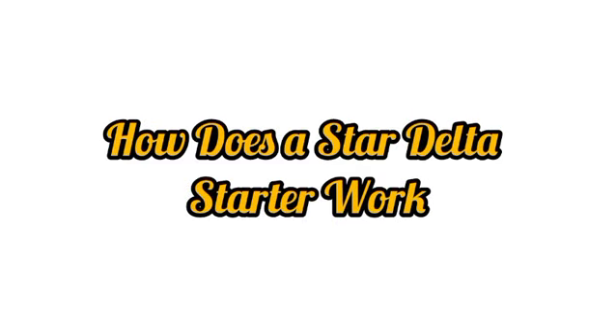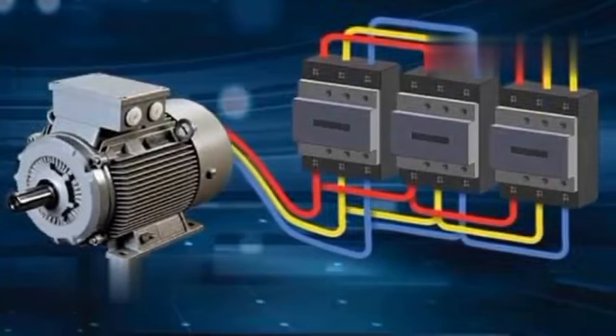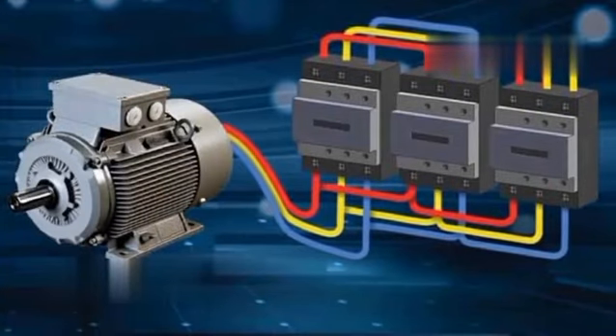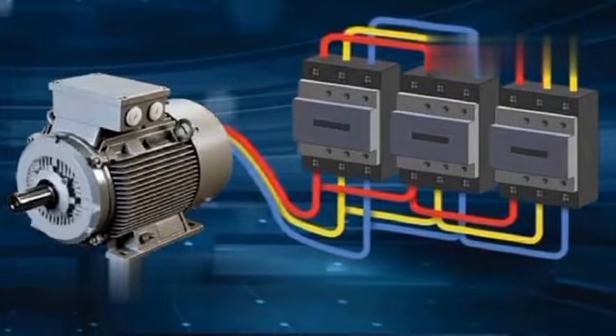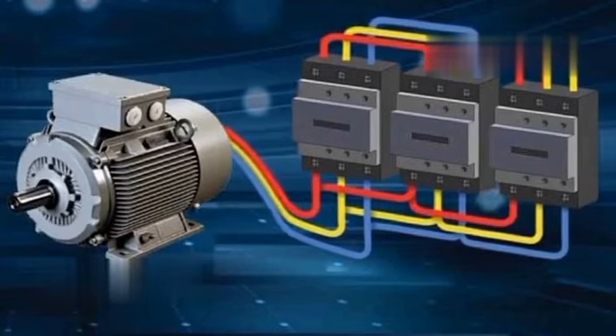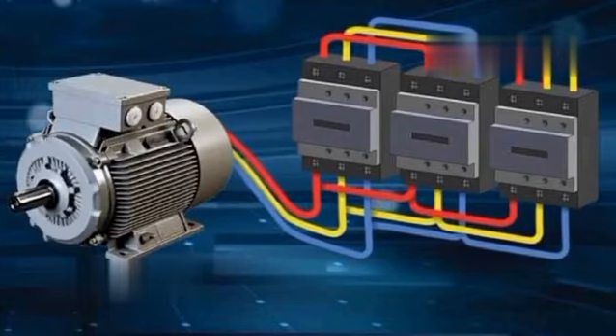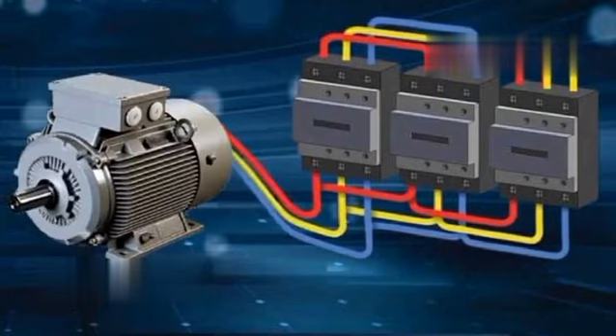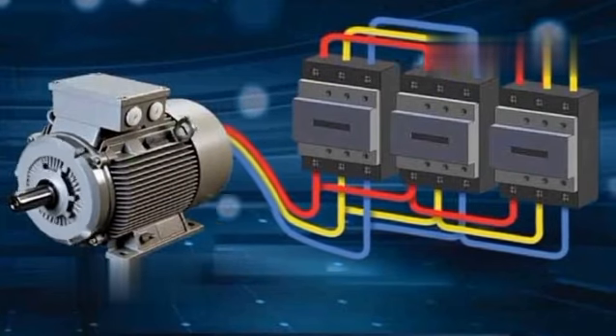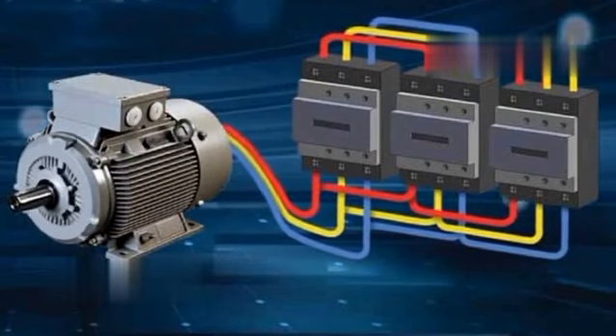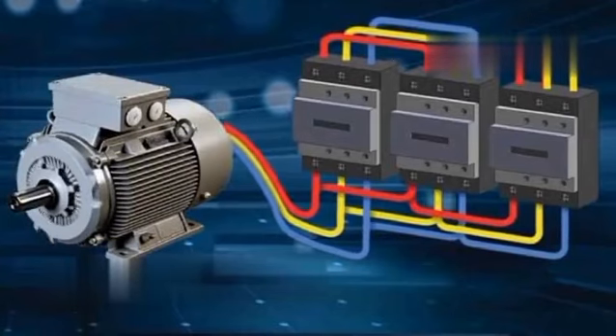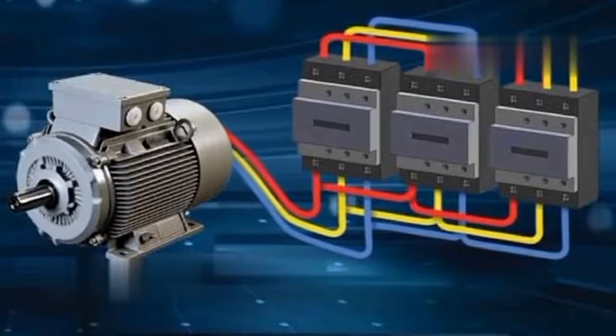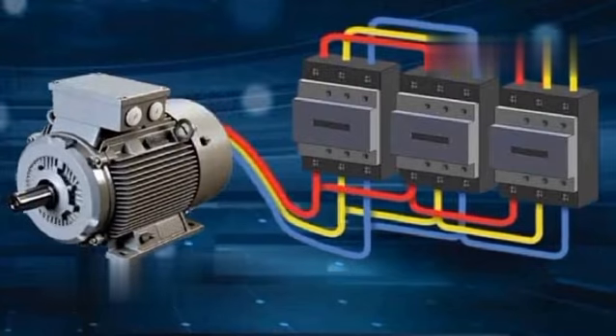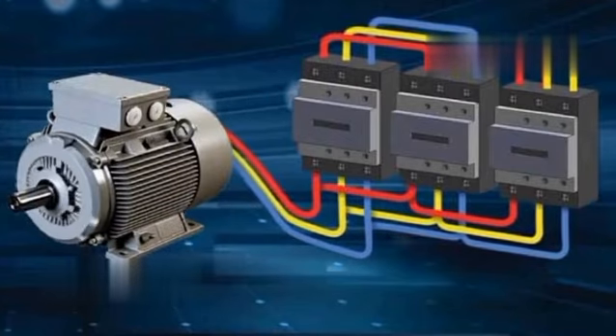How does a star delta starter work? To explain how does a star delta starter work, the process begins with reduced voltage in star mode and later shifts to full voltage in delta mode. This transition is automatic. The staged operation protects the motor and electrical system while ensuring smooth acceleration and controlled startup performance.